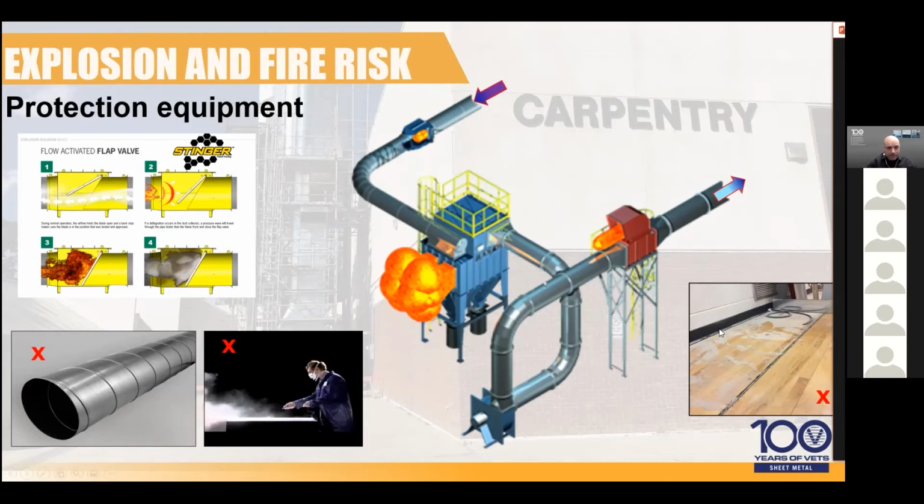If you look again at that picture, any fuel in the building will create that potential for an explosion. In NFPA 664, which is for wood, it is allowed to have up to 5% of the surface being covered at 1/8 of an inch. If you're above that, then your area becomes classified electrically. So it requires additional protection for your Group 20 in the electrical code, which is explosive.